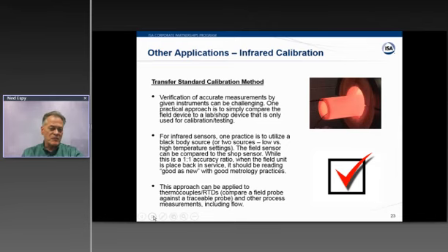And if the field sensor's off, maybe all you have to do is clean the lens, and you'll see the temperature go up. But do keep in mind that this type of test is really a 1-to-1 accuracy or test uncertainty ratio. You're going to have some wider latitude on how accurate you can be and when you should make an adjustment. But the idea is that if the shop sensor is reading a temperature, when you make an adjustment to that field unit, all your field units are going to be matched to your master in the shop, and it's going to allow you to make consistent, good measurements and try to get it back into good as new.